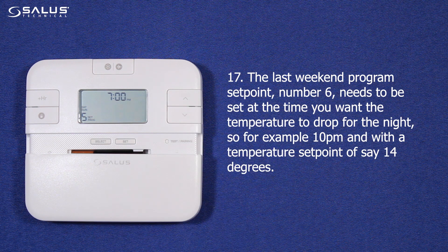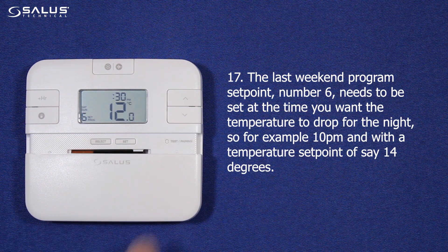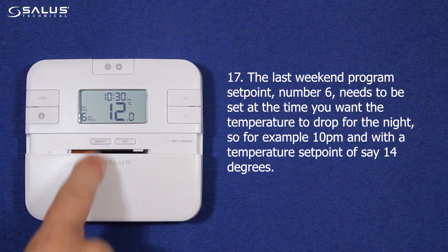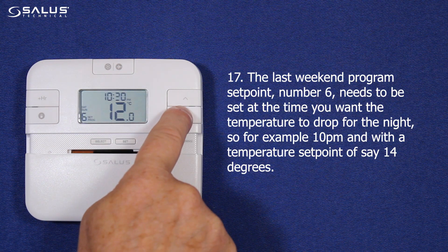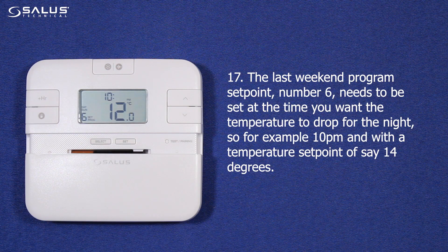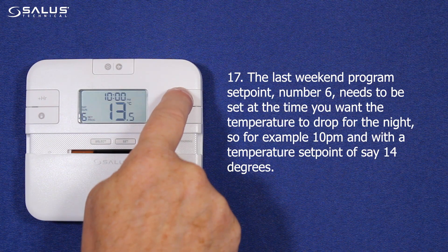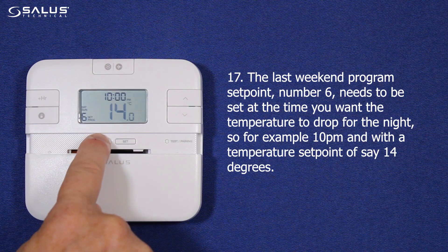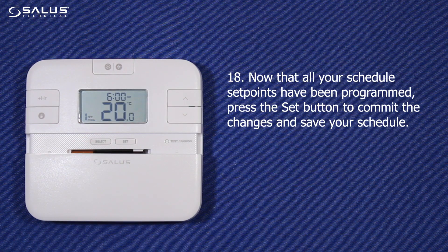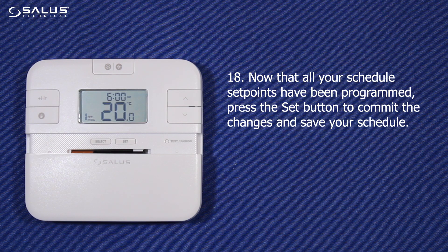Step 17: The last weekend program set point, number 6, needs to be set at the time you want the temperature to drop for the night, so for example 10 p.m., and with a temperature set point of say 14 degrees. Step 18: Now that all your schedule set points have been programmed, press the set button to commit the changes and save your schedule.